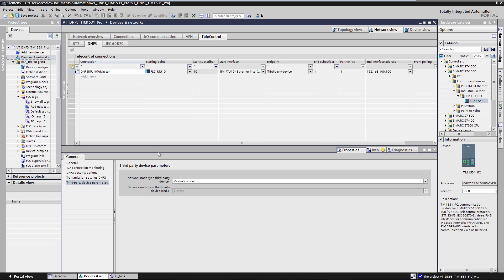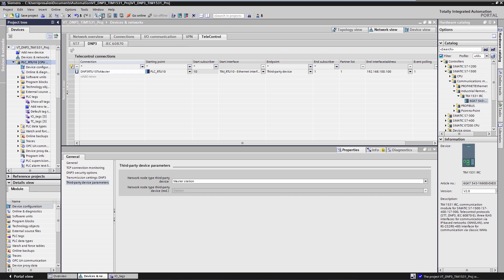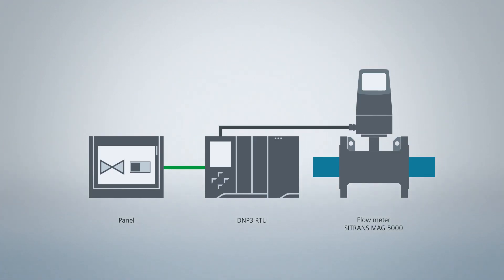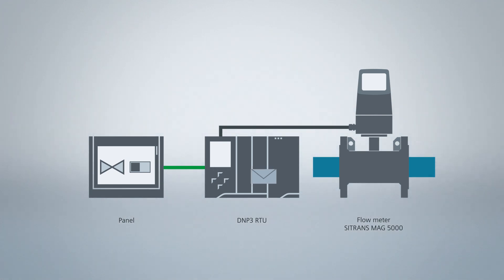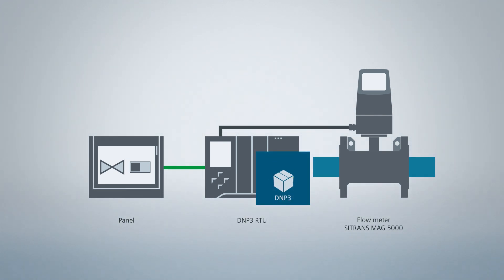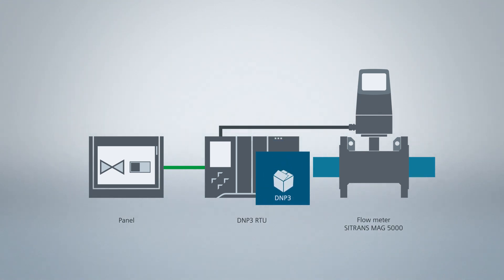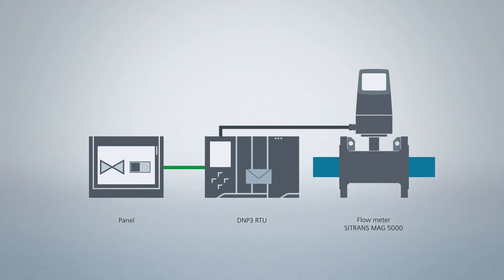Now I can compile the configuration and load it into the CPU as well as the TIM. The DNP3 control center is thus capable of establishing a connection to the RTU 10. However, no process data is transmitted yet. In order for our process data to be sent from the RTU to the DNP3 master, we create so-called data points in the data point editor for the TIM. A data point is a DNP3 object. It is read by the TIM from the S7-1500 CPU and then transmitted as a process value via the DNP3 protocol.